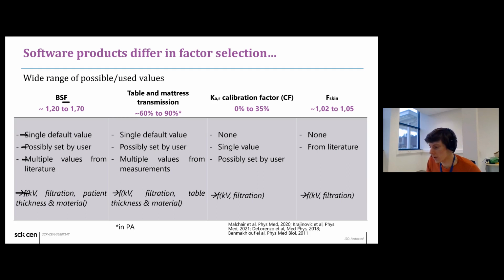And you can see that the range of possible backscatter values is large. So a possible 50% error, which means possibly a 50% error in the skin dose. But that's also the case for the table and mattress transmission. You can see here that the transmission value is about 60 to 90%. And if you consider a lateral projection where there is no mattress or table in the beam, it's even 60 to 100%. So again, between the two extremes, it's even about 100% difference.